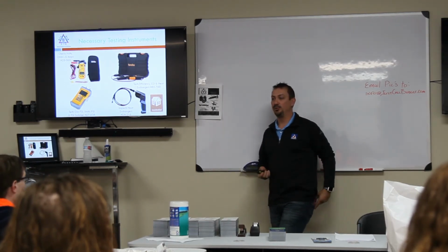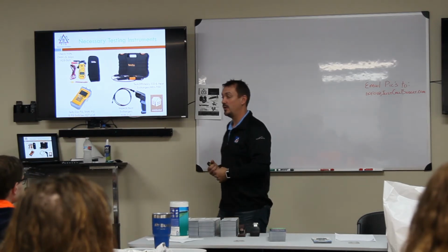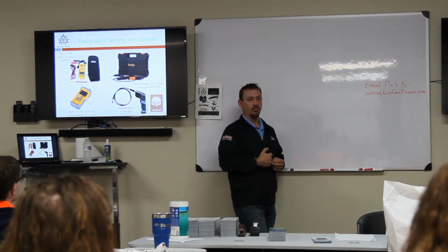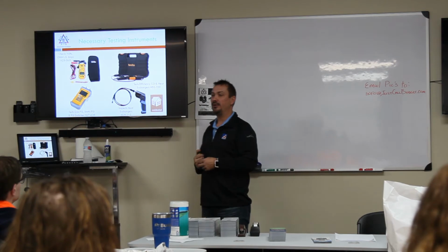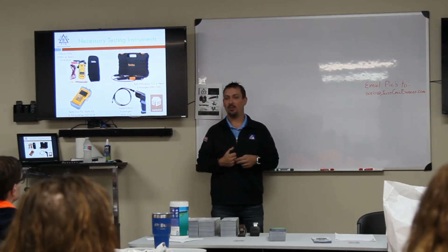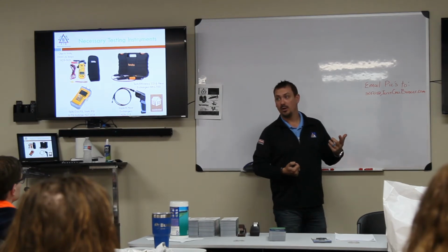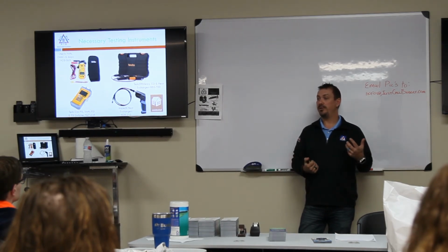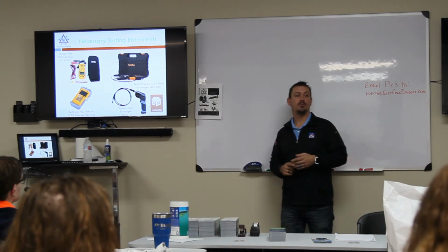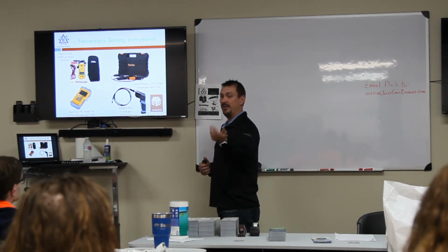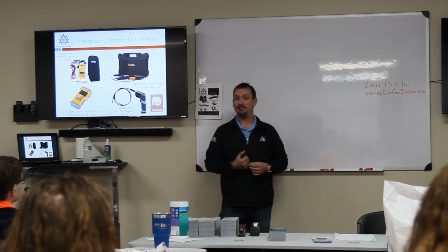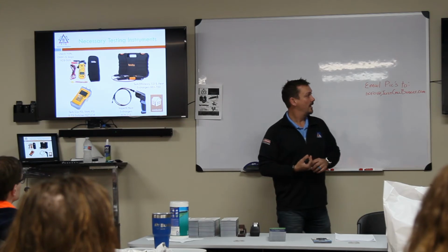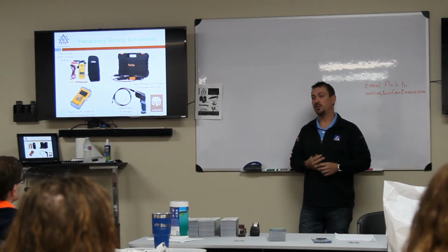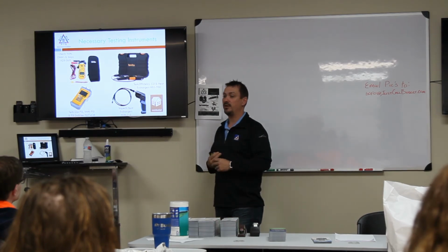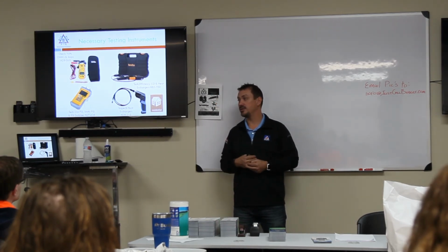Now all of our devices have Bluetooth capability or Bluetooth hookup to our phones. And I didn't necessarily see the benefit of having a meter hooked up to my phone until we were at a job and we wanted to check the amp draw off the blower motor when it was running. Well, it's kind of hard to do with the door off. So that was one of the features that I was able to use: hook it up, leave the meter inside the unit, close that door, and see what the readings were with the door closed. They've come a long way in their tools, and that is a truly HVAC meter right there that can do just about anything that we're going to need or want for our systems and our equipment.